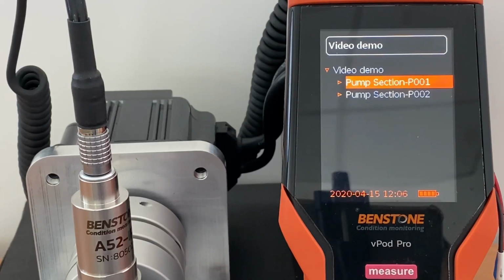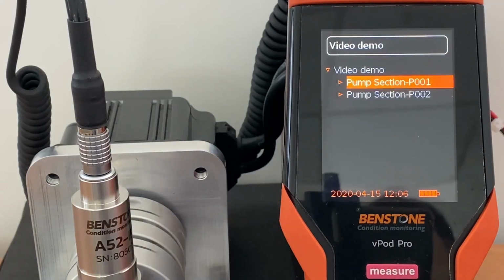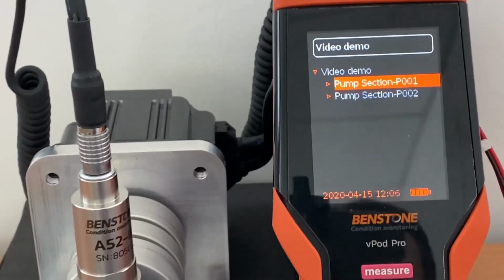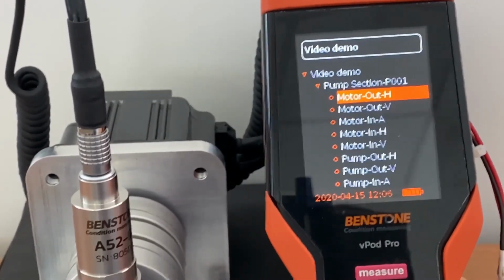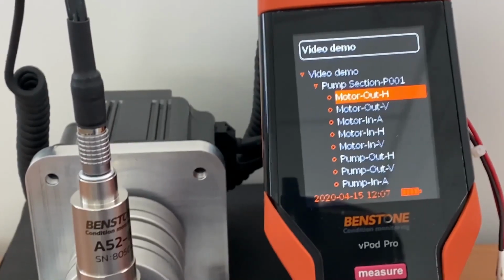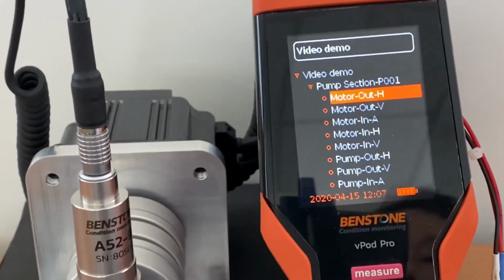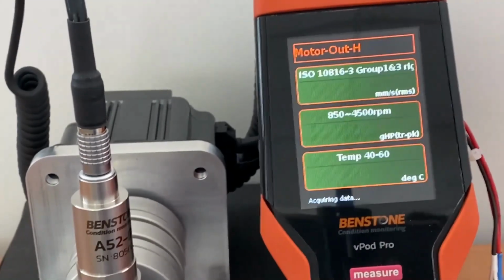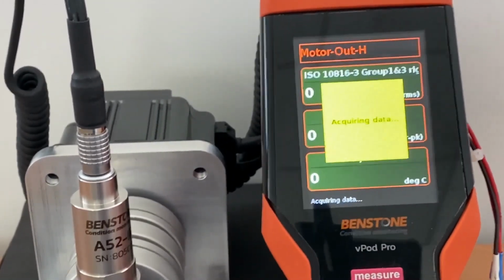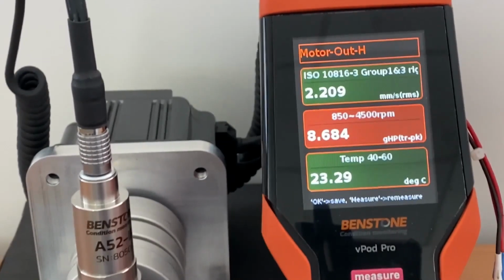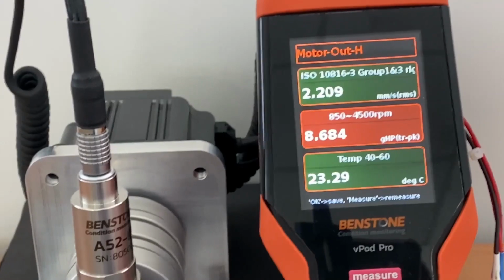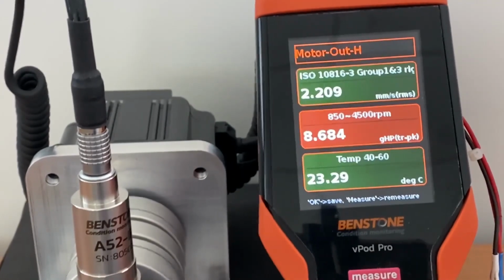Select video demo, and once selected, you will notice that we have 2 points, pump section P001 and pump section P002. Next, I will turn on the rotor kit, and then I will select the first point, motor out-H, horizontal, and then press the measure on the vPod Pro. At this time, the vPod Pro will measure and acquire the data. Next, press the OK button to save the data, or press measure again to retake the measurement.